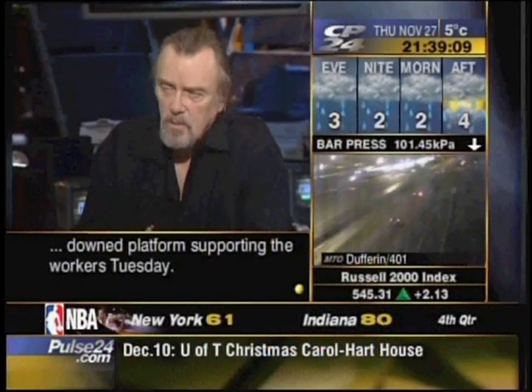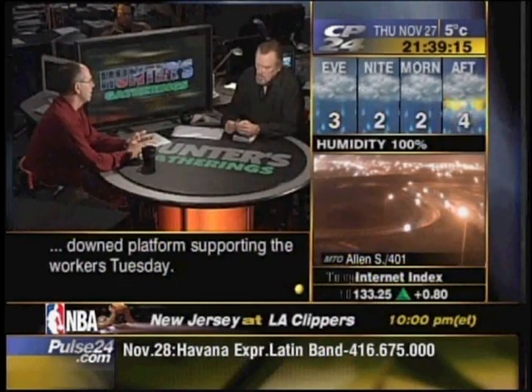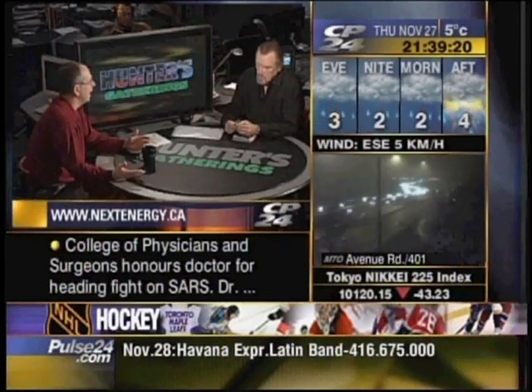So it releases its energy. For every unit of energy it takes to do that, you get 4.5 units of heat. In cooling, since the ground's cool, it's much easier to cool, so you use about half the energy for cooling. At the same time, you're taking the heat out of the house. We don't just throw it away, we put it in the hot water tank. It's real simple stuff.